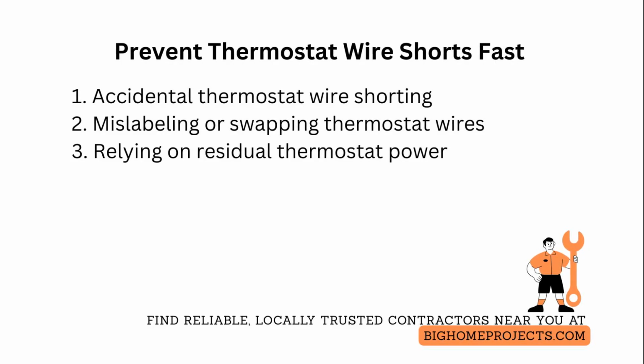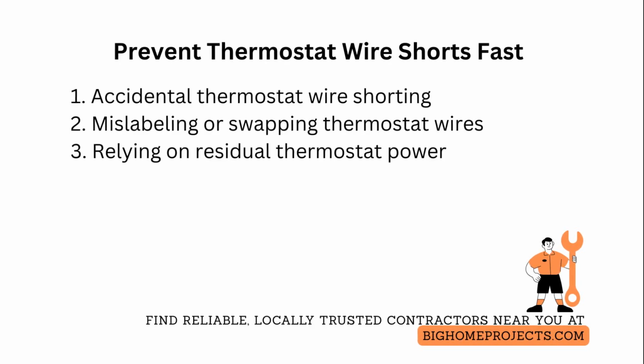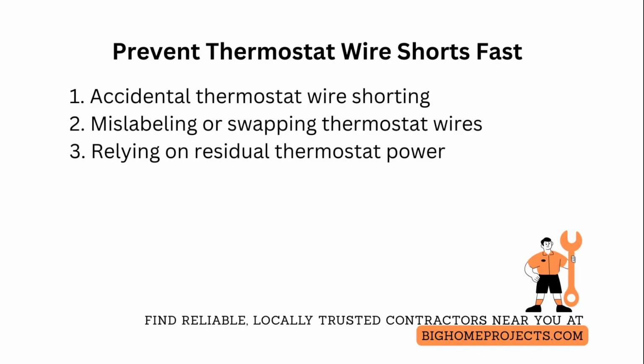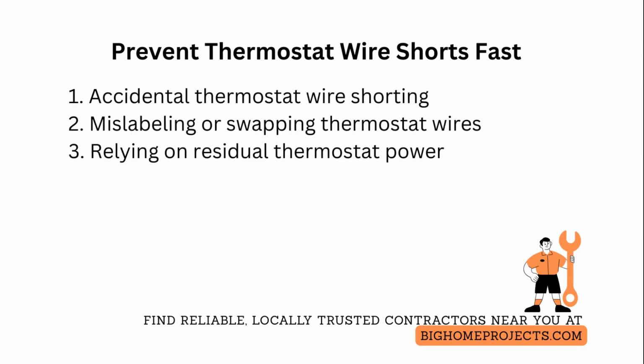The third frequent problem is relying on thermostat batteries or residual power while working, which can lead to shocks or control shorts. Always confirm zero voltage with a tester at both the thermostat and the furnace control board before handling wires.